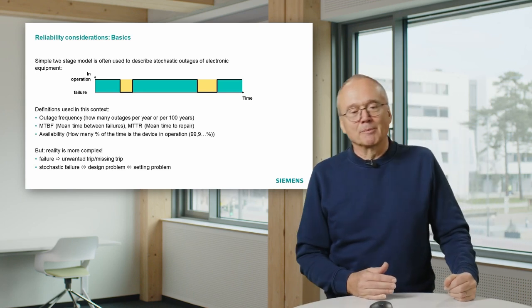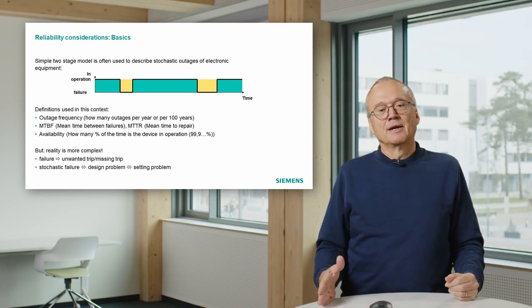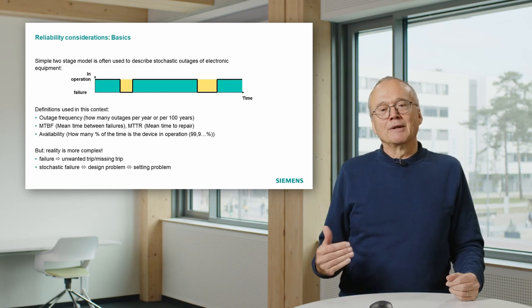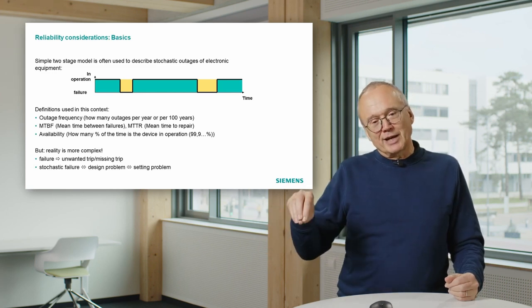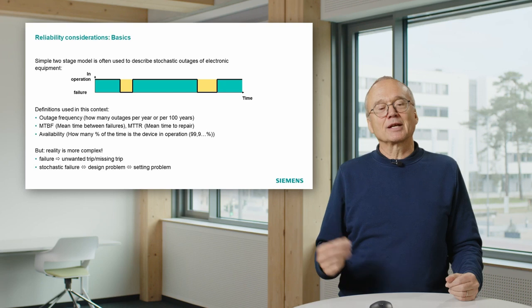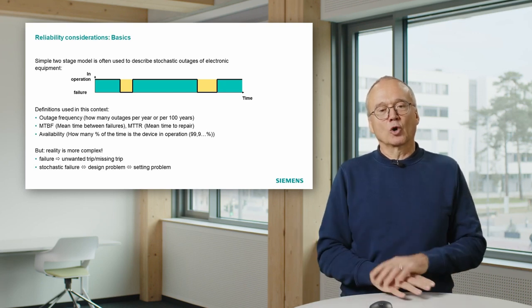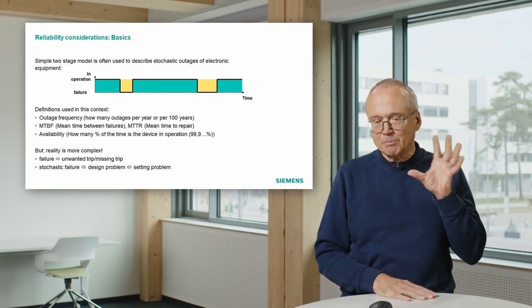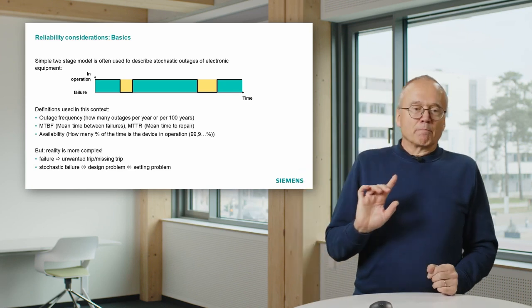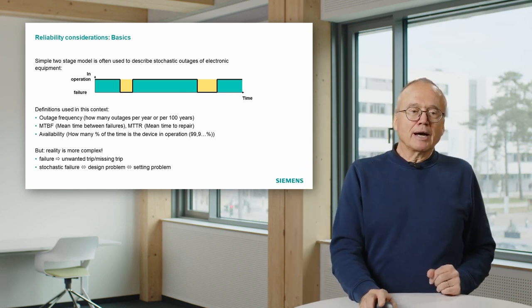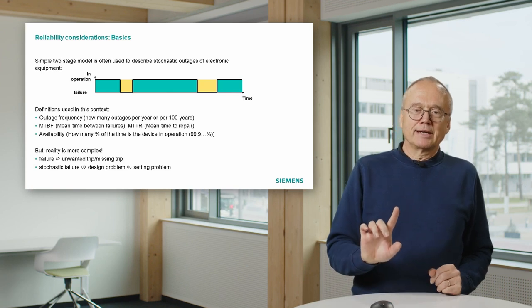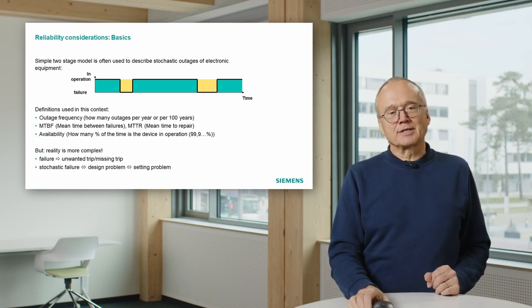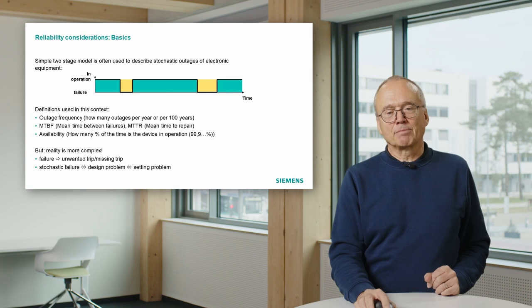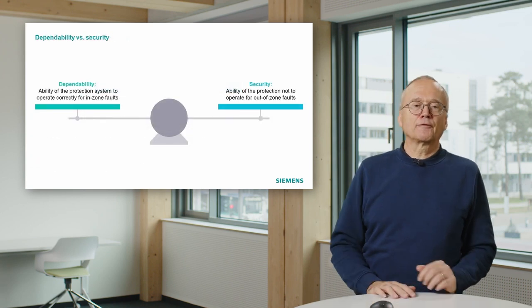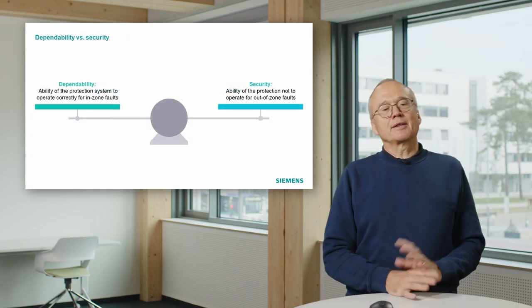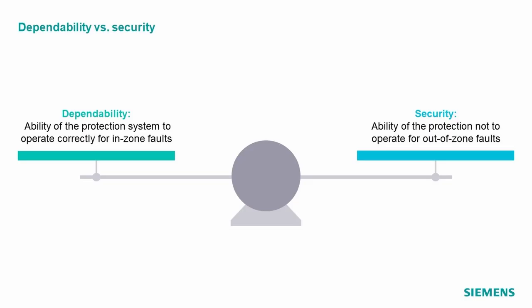Or if you have a setting problem, this problem is always there, but it becomes only visible if you have a fault at a location where this setting problem results in a wrong reaction. And this has to be taken into account. Before we look into that a little bit deeper, I just want to introduce two terms in this context. Unwanted trip and missing trip are two terms which are often used in protection, and then there are the terms dependability and security.